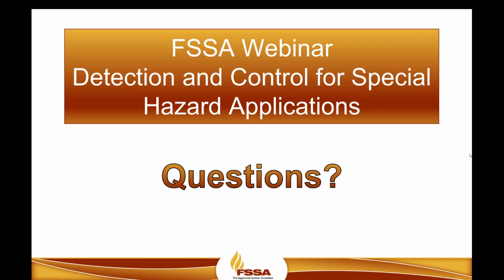All right, so the next question is mercantile occupancy, which was an unexpected finding. Are there any specific types of mercantile occupancies where aspirating detection might be appropriate? I would absolutely say yes. I believe that we are really on the verge of seeing an increase in air aspiration detection because of its ease of installation, and some manufacturers have gone from pipe to tube. The testing of these systems, the single point, the communication capabilities, we are starting to see more in commercial applications than we had in the past, where it was primarily industrial. But no, I believe we're going to see a lot of growth in that area in the years to come. I would agree, Jeff. We're seeing it pretty much applied in all areas of detection.